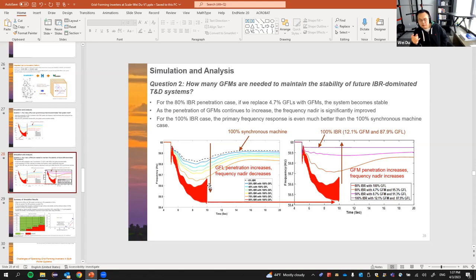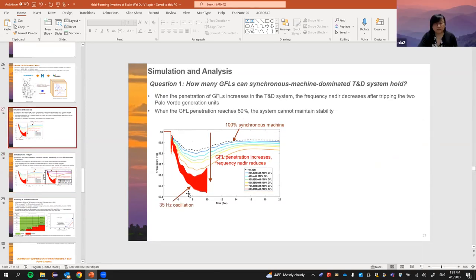First question is, in GridLAB-D, the simulation time step is also 1 millisecond. So that's for the dynamic simulation. And for the stability, as you can see, when the penetration level goes above 70%, we see this 35 hertz oscillation. That was what I mean by unstable. So this 35 hertz oscillation actually comes from the transmission level.